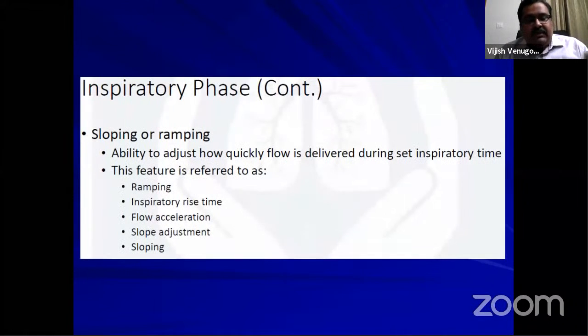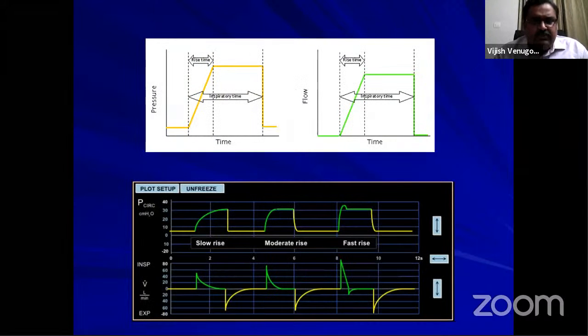Another very important thing that is affecting the inspiratory phase is the ramping or sloping. This is the ability to adjust how quickly flow is delivered during the set inspiratory time. This is referred to as the inspiratory rise time. So these are some additional points that we are adding into the principles. If you look here, from the baseline, from the initiation of your inhalation till the limit is reached, this time is referred to as the rise time.